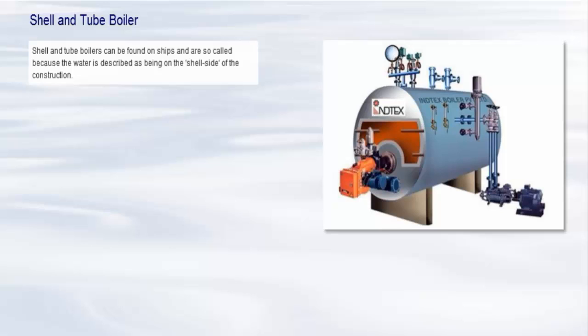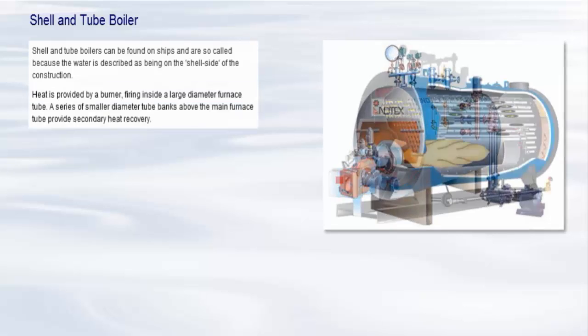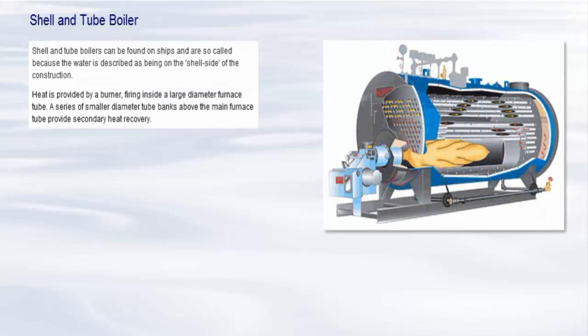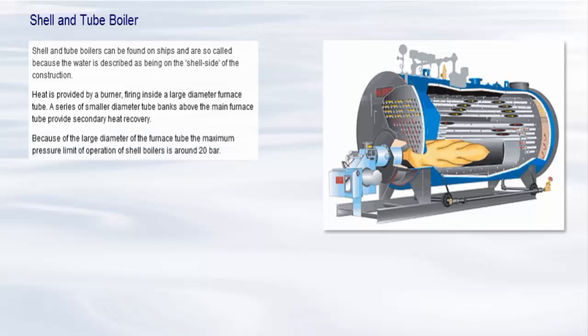Shell and tube boilers can be found on ships and are so called because the water is described as being on the shell side of the construction. Heat is provided by a burner firing inside a large diameter furnace tube. A series of smaller diameter tube banks above the main furnace tube provides secondary heat recovery. Because of the large diameter of the furnace tube, the maximum pressure limit of operation of shell boilers is around 20 bar.